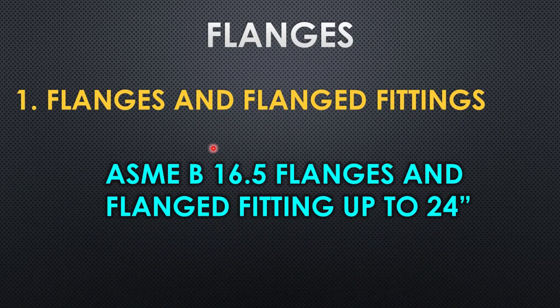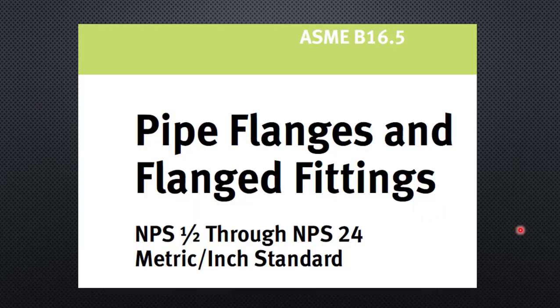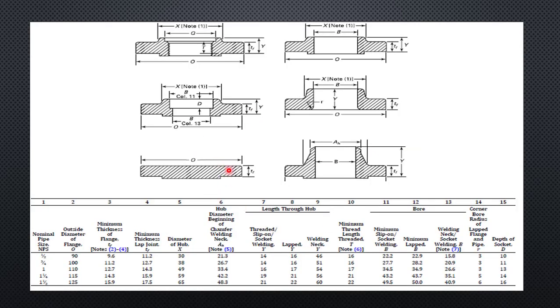The first is standard flanges. The dimensional standard we are referring to is ASME B16.5, and the description of this standard is flanges and flanged fittings up to 24 inch. The title reads: Pipe Flanges and Flanged Fittings, NPS half inch through NPS 24 inch. This is available in both metric and standard. If you open the standard you will be able to see the entire dimensions of all types of flanges — threaded flanges, slip-on, weld neck, and blinds — with end-to-end dimensions of every parameter.